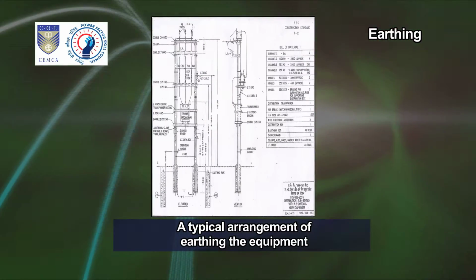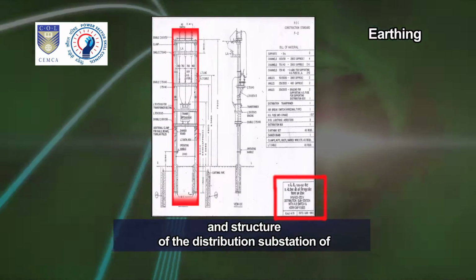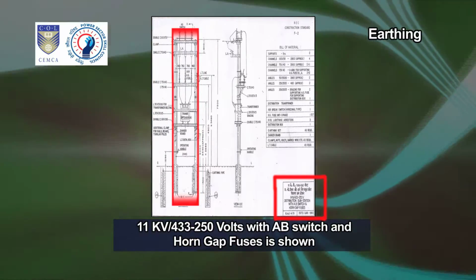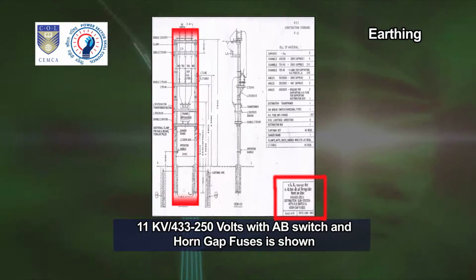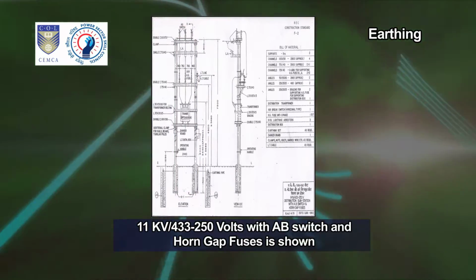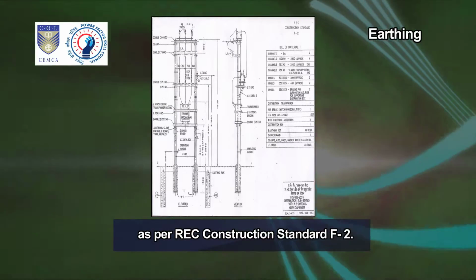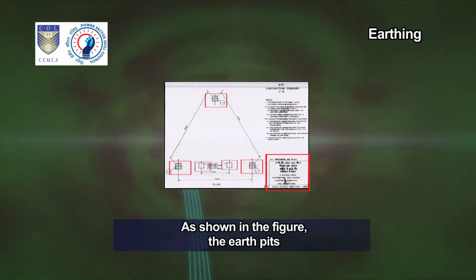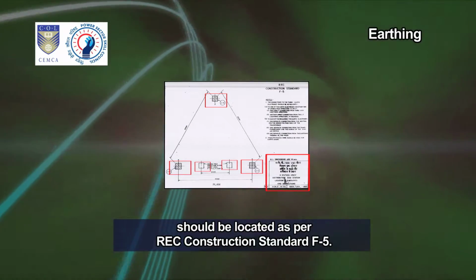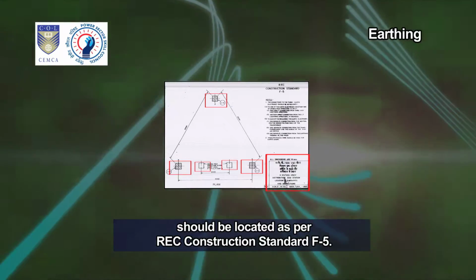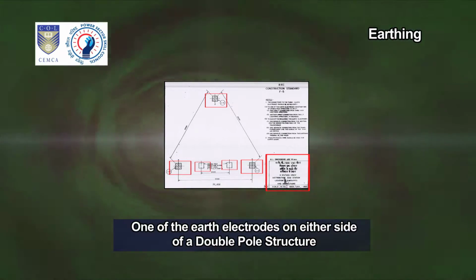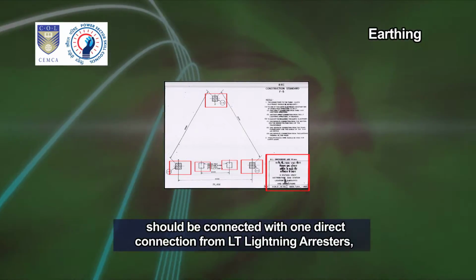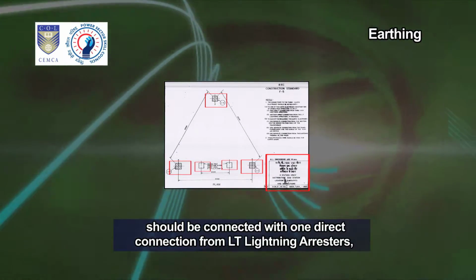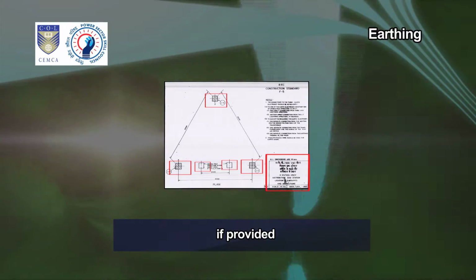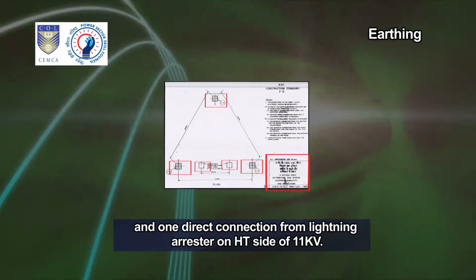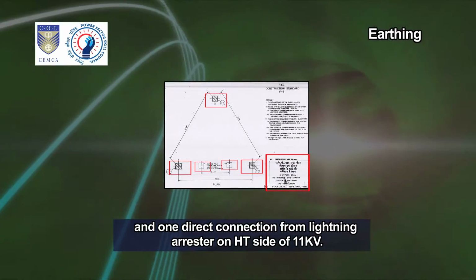A typical arrangement of earthing the equipment and structure of the distribution substation of 11 kV by 433 to 250 volts with AB switch and horn gap fuses is shown as per REC construction standard F2. As shown in the figure, the earth pits should be located as per REC construction standard F5. One of the earth electrodes on either side of a double pole structure should be connected with one direct connection from LT lightning arresters, if provided, and one direct connection from the lightning arrester on the HT side of 11 kV.